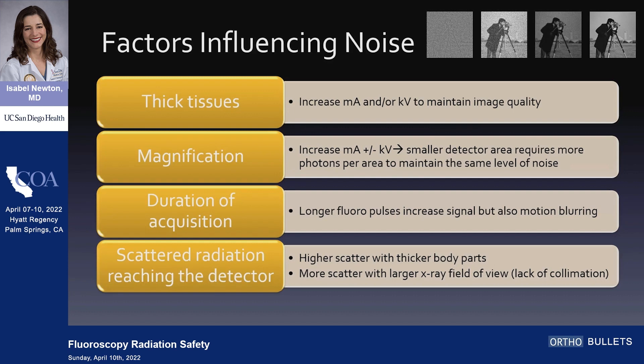Factors affecting noise are thick tissues, magnification — because you're having to drive these photons through a smaller area — and the duration of acquisition. Longer fluoroscopy pulses or longer acquisition times are going to have higher noise if there's motion blurring. And then scattered radiation: if it bounces off of you and hits the detector, those are nonsense photons that add more noise.